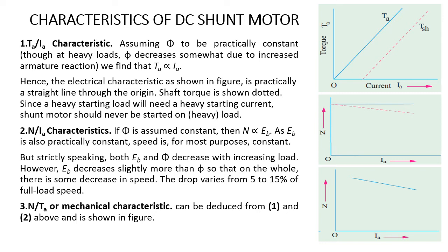Shaft torque is shown dotted since a heavy starting load will need a heavy starting current. A shunt motor should never be started on a load.